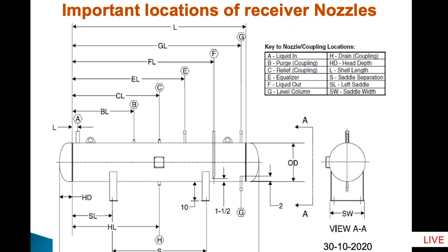If you can see, the purge coupling, try to keep the purge connection as far away from the liquid inlet as possible, because the liquid inlet has a mixture of ammonia vapor and ammonia liquid when it comes into the receiver, and we do not want ammonia to be wasted in the purge line. So the purge connection should be as far away as possible.